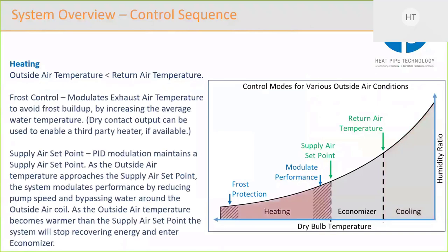The next regime is heating. So in this case, the outside air is cooler than the return air. It's also below the supply air set point, so the system is trying to maintain the set point. So what it's doing is it's using PID modulation. And first of all, it controls pump speed. And then when the pump is running at minimum speed, then it starts to control the valves to put extra bypass in and to put extra resistance in line with the coil.